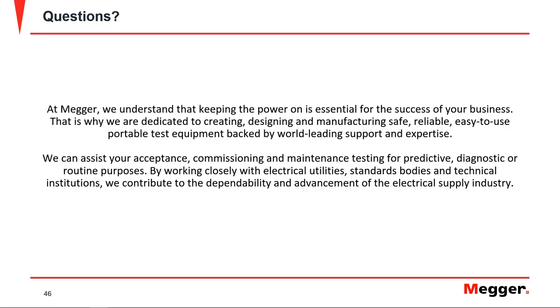All right, thank you. Sanket, could you please shed some light on the pros and cons of primary versus secondary injection? Yeah, so primary injection is where you actually inject current through the breaker, whereas secondary injection testing is another form of testing where the signals are fed to the trip unit without actually injecting current through the breaker. Now there are pros to using secondary injection. Let's say you're testing a really big power circuit breaker. You do not need a high current test set for that. You can just get a small secondary injection unit and carry out secondary injection testing on that.